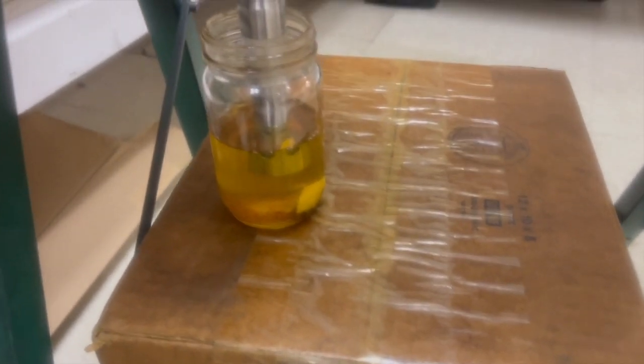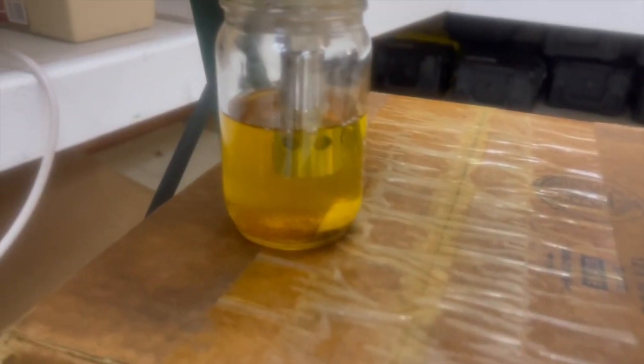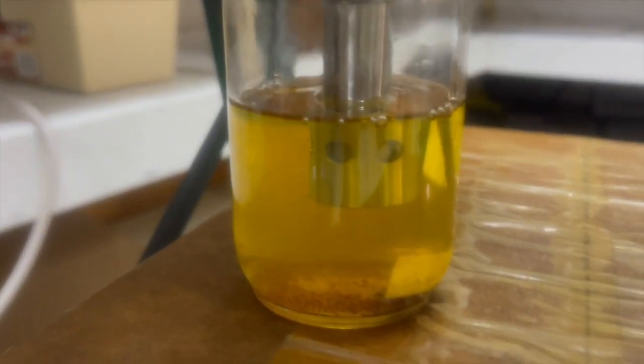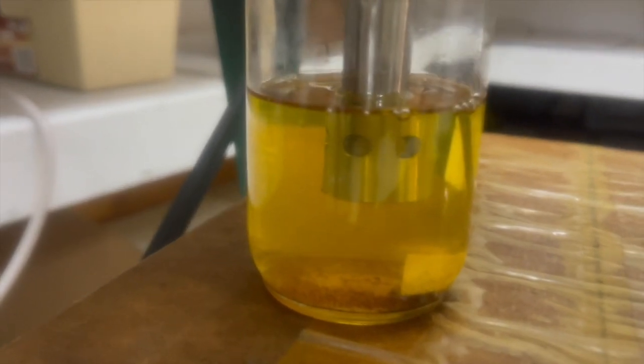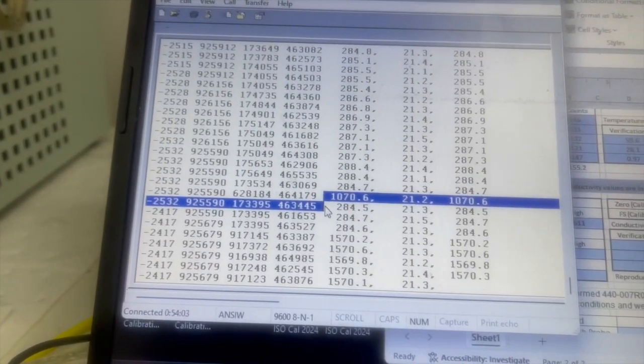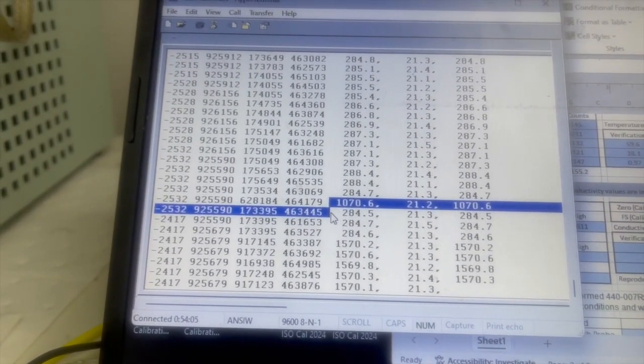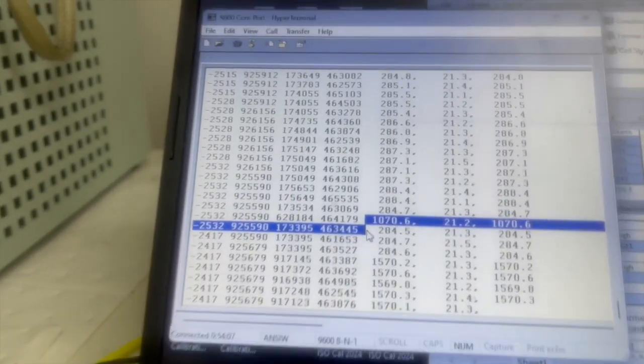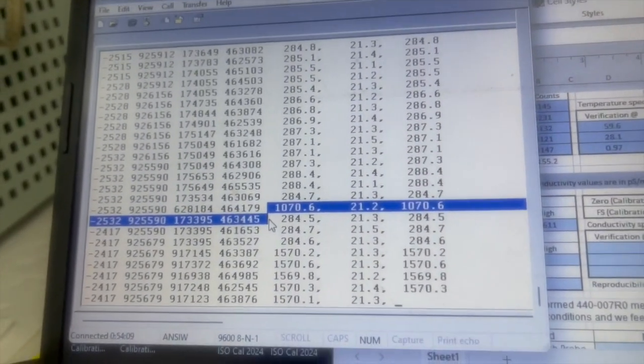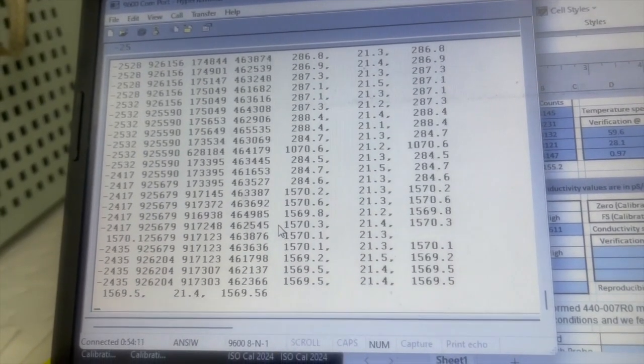Okay, so we've placed our sample on the sensor, and just make sure that the sensor tip is submerged so that you can see the holes in the sensor tip like that. And we're going to go over here and see what values we're getting. And we're at about 1570. So that tells me we need to adjust the inline sensor upwards.